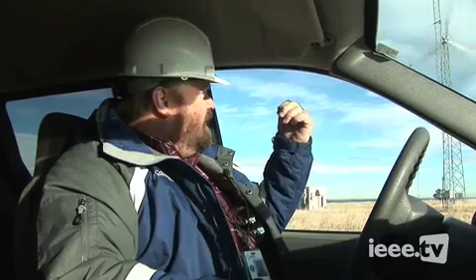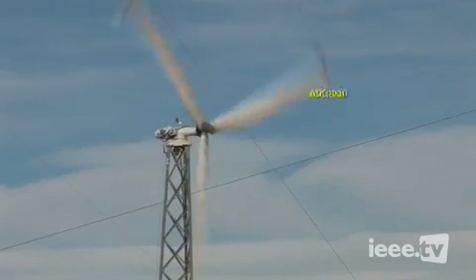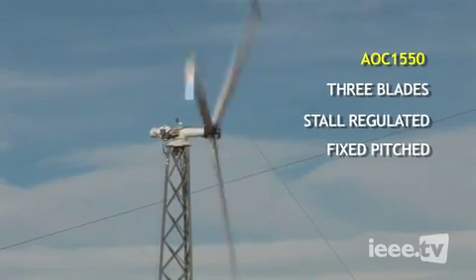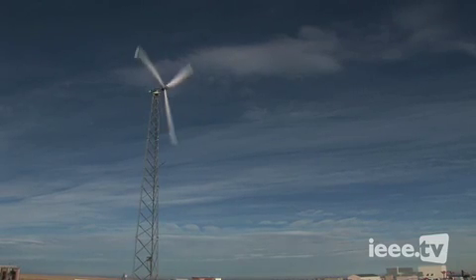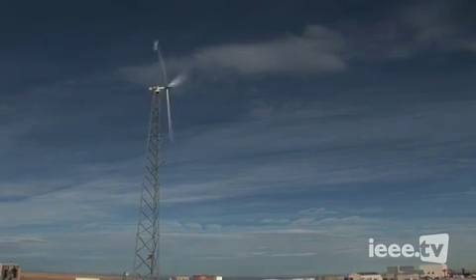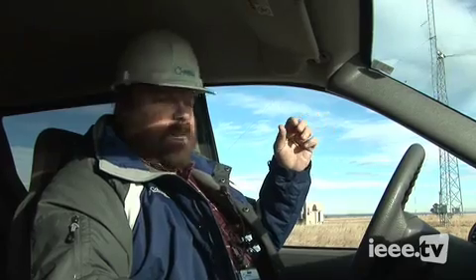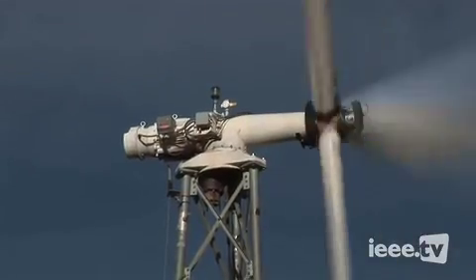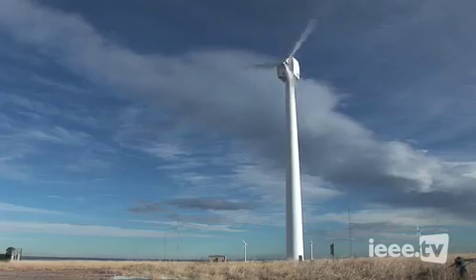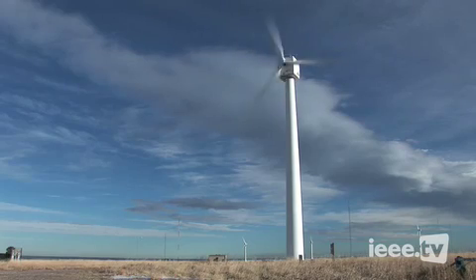The first machine here on our left is the AOC 1550. It's a three-bladed, stall-regulated, fixed-pitched machine that's a relatively old design — 20 to 25 years old — but is very good in cold-weather environments and consequently is installed in places like Kotzebue and Wales, Alaska. It's a 50-kilowatt name-plate rated machine, relatively small to medium-sized, but it's simple and works very well without a lot of maintenance.